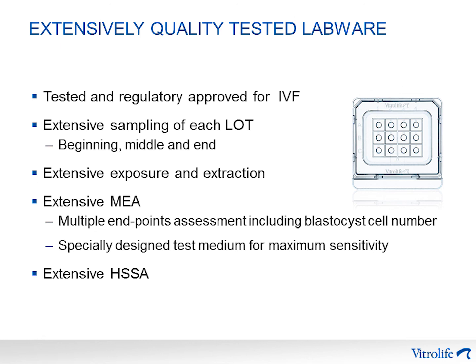To avoid this, samples for QC testing are always taken from the beginning, from the middle, and from the end of production. When it comes to the exposure and extraction procedure during testing, the general principle is that the sample exposure should mimic the way a product is used at the clinic, according to the instruction for use. We follow the principle of worst case scenario to make sure that the products we test are properly exposed. The timing has to be long enough to guarantee that you extract potential toxicity if that is present. As mentioned earlier, we always use a specially designed test medium for these types of tests. That is to maximize sensitivity.